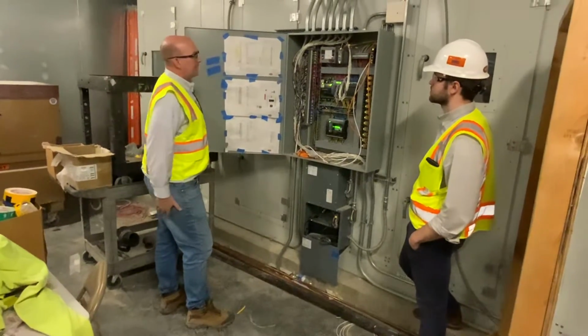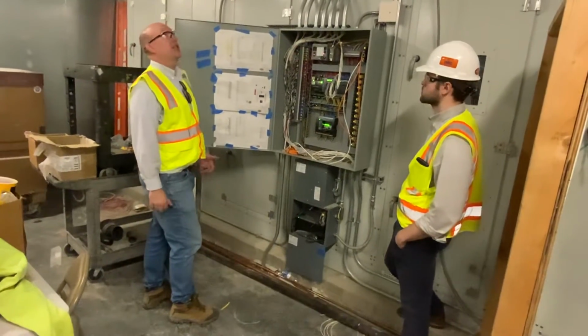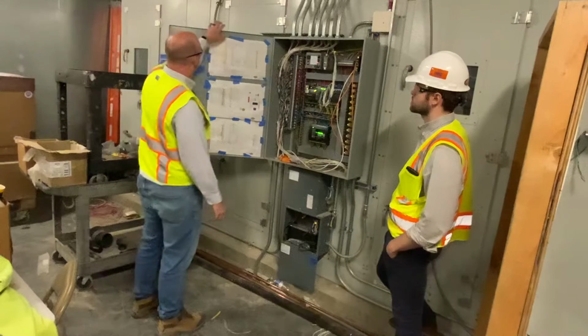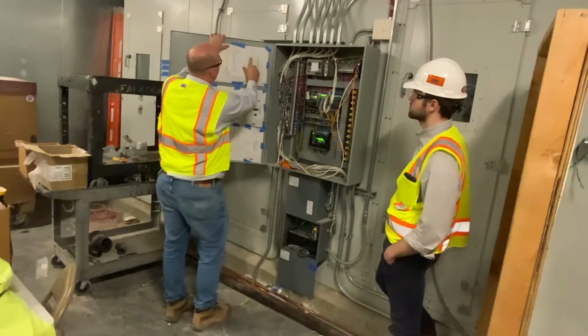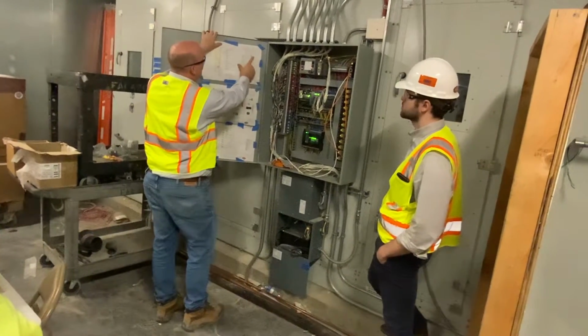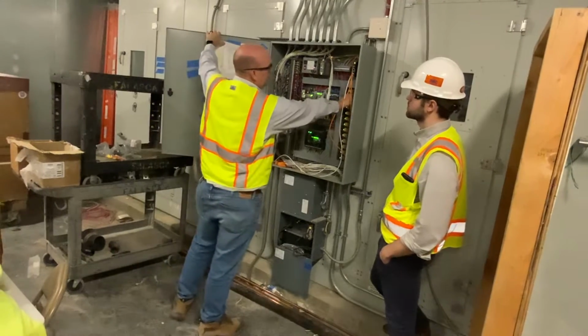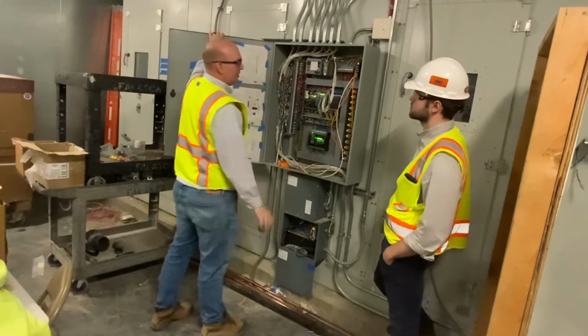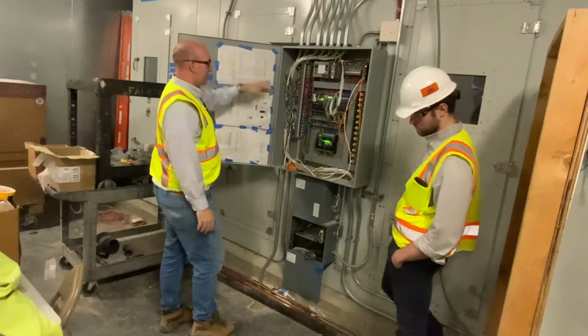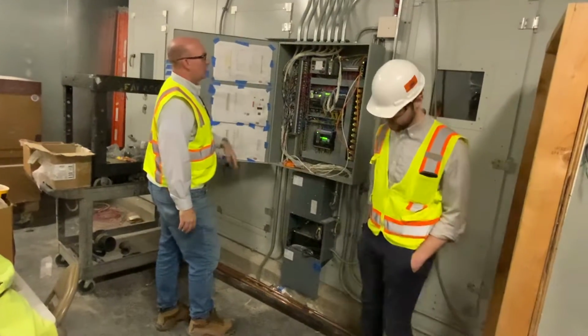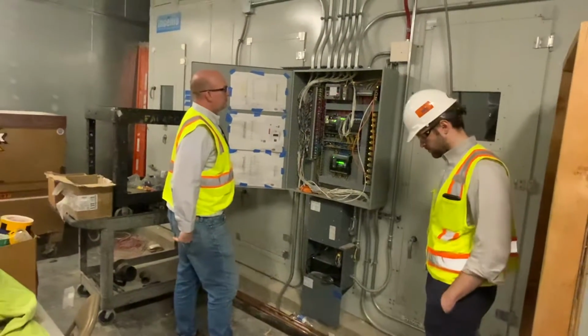If you did want to shut down a unit or run a test and say, hey, does the logic work with the smoke detector? Come over here, I find a fire alarm system relay, I should say. That's safety relay number 2. I can pull the block and it'll kill the safety circuit, and the whole unit will shut down.